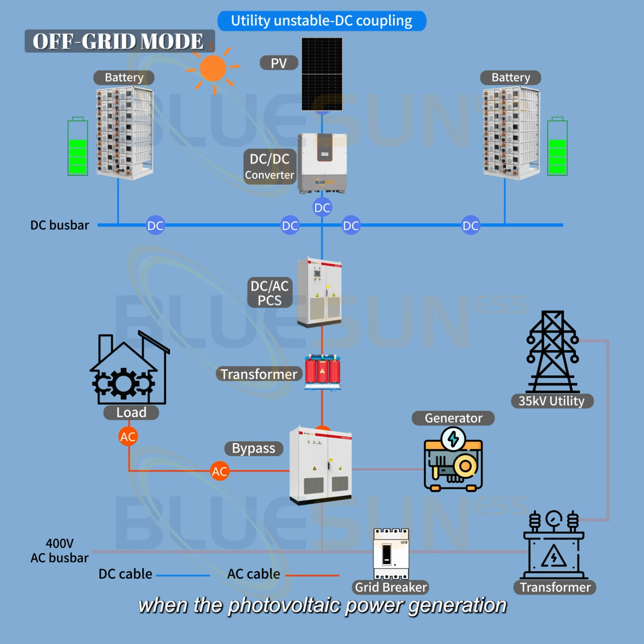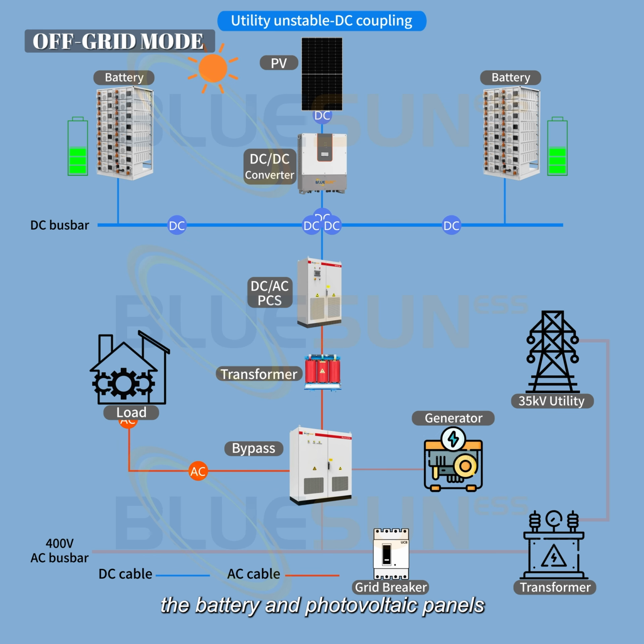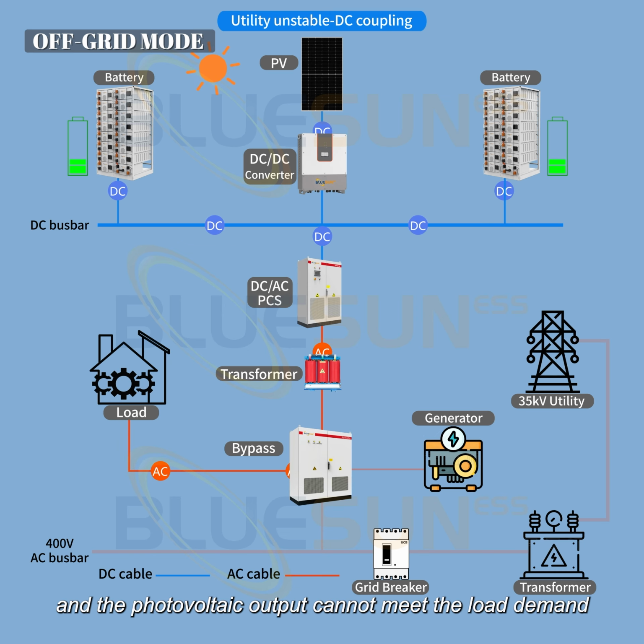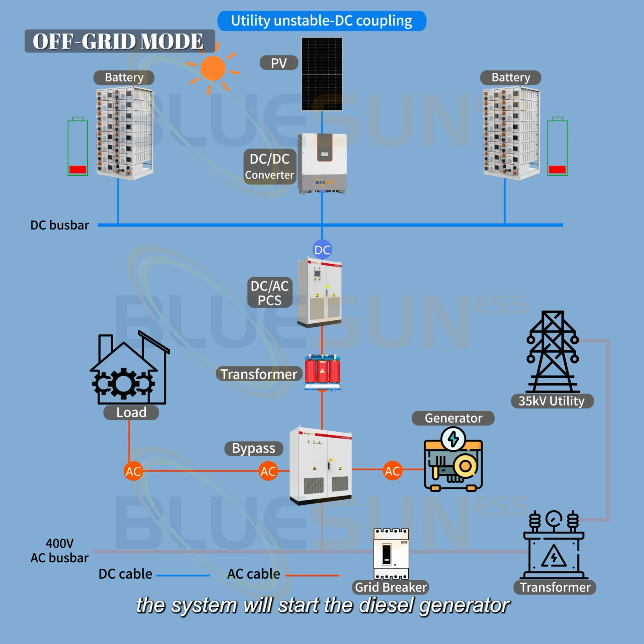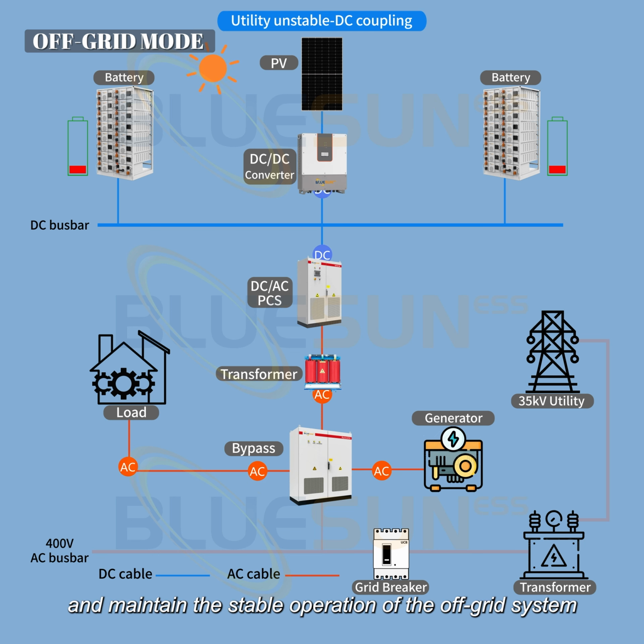When the photovoltaic power generation is lower than the load demand, the battery and photovoltaic panels will jointly power the load. If the battery power is insufficient and the photovoltaic output cannot meet the load demand, the system will start the diesel generator to power the load and maintain the stable operation of the off-grid system.